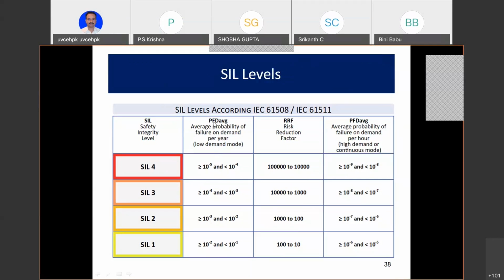So the average probability of failure on demand, that the safety system will fail, if you have got a SIL 4 category, the rating of that entire installation with all the transmitters and valves, everything put together, is between 10 to the power of -4 and 10 to the power of -5. That is one failure in 10 to the power of 4, one failure in 10 to the power of 5 years. In between, it will swing. What about the lowest? 1 by 10 and 1 by 100.